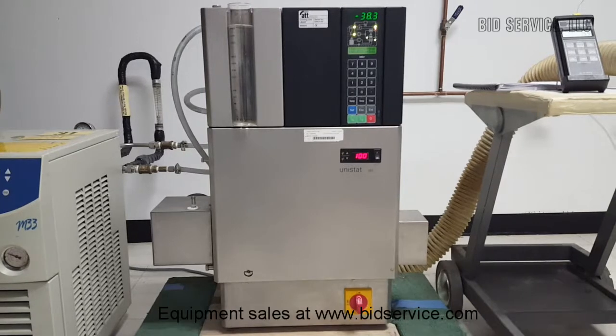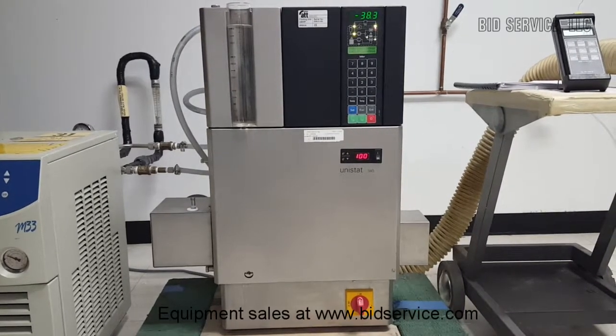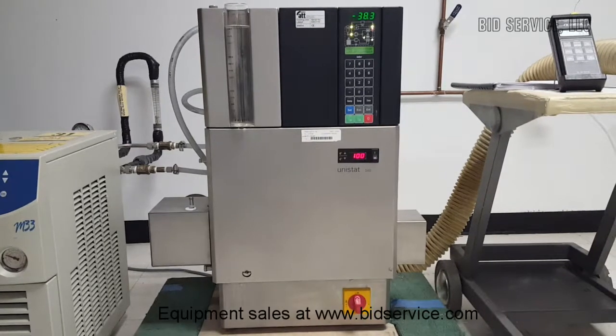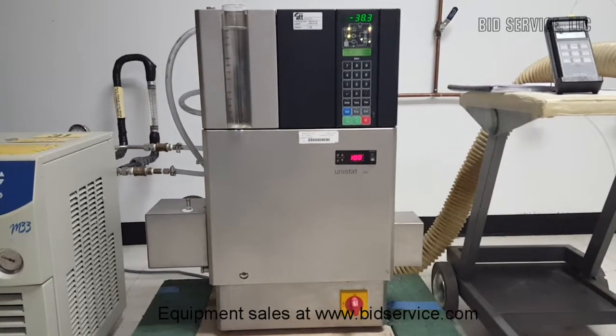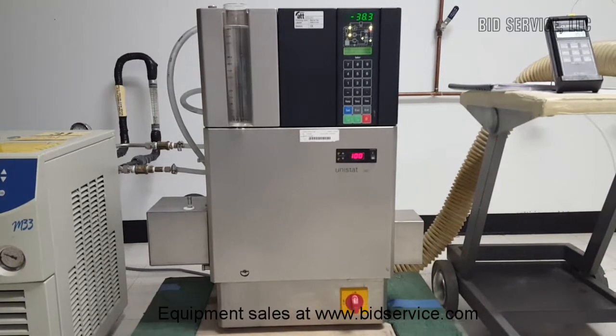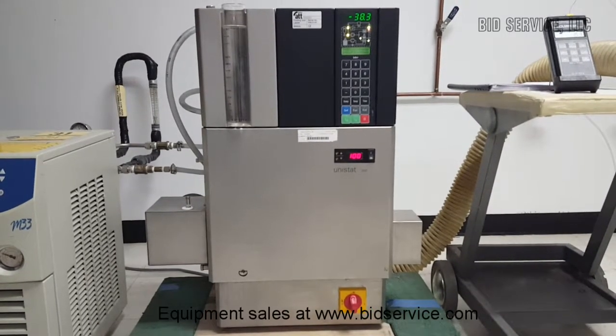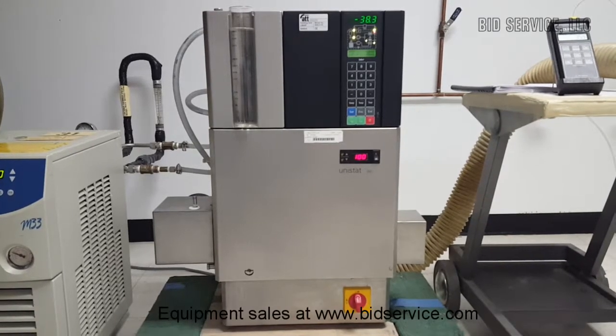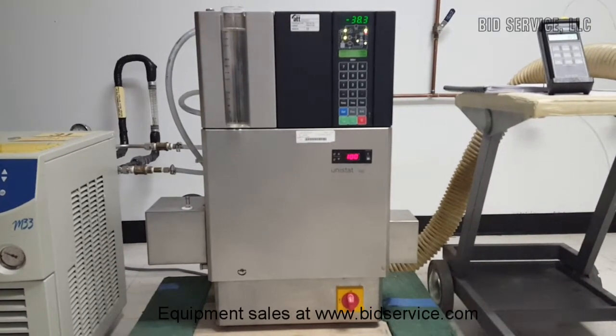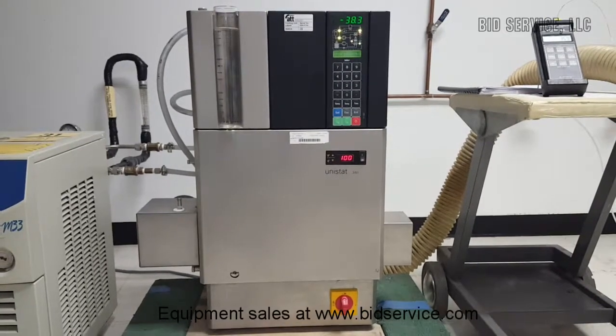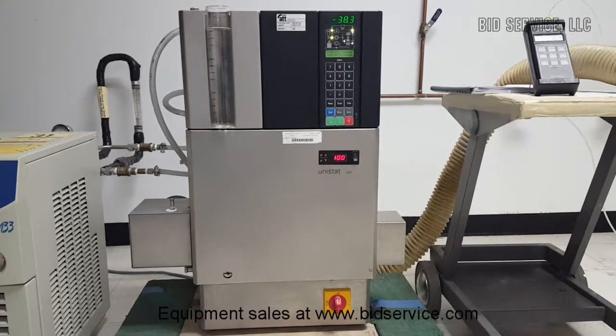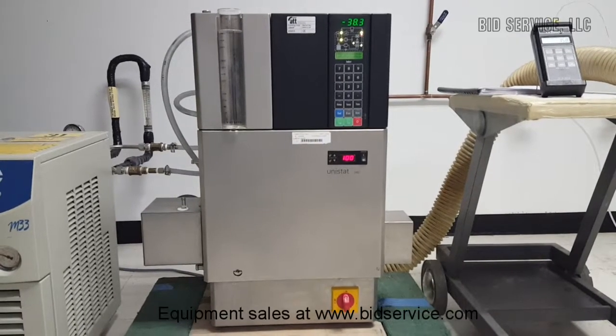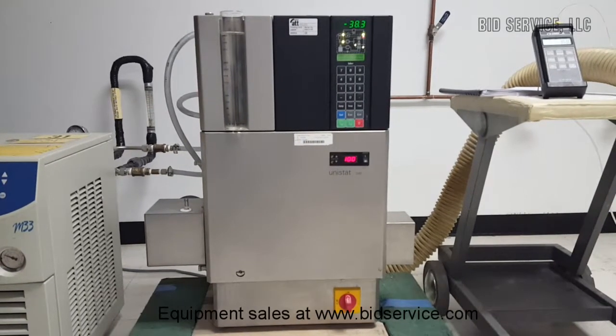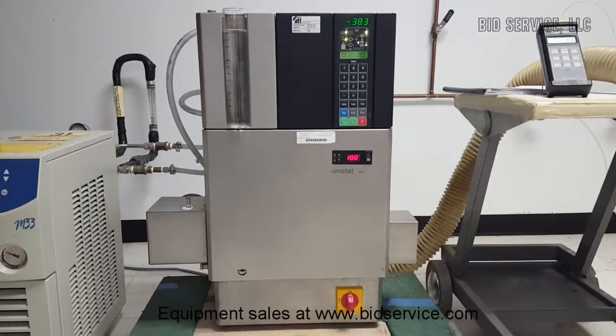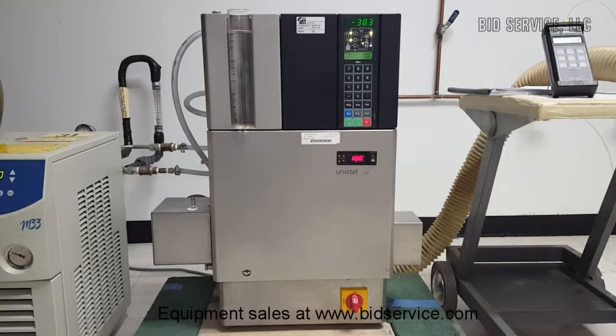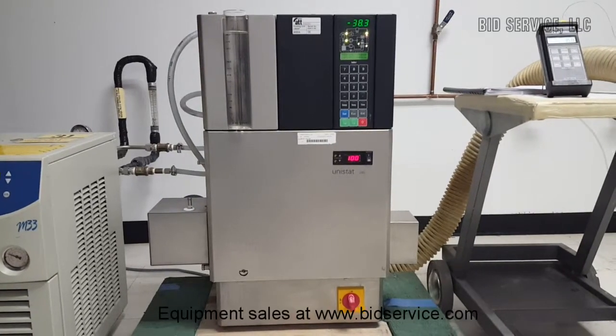Unistat 340 PV S35 precision recirculating chiller. It has a digital controller, a cooling capacity at 0 degrees C of 1 kilowatt, a heating capacity of 1.5 to 3.0 kilowatts, a temperature range of between -40 to +200 degrees C, a pumping speed of 20 liters per minute. It is an air-cooled refrigeration compressor. The unit operates on 208 volts AC, single phase, with an 18 amp service.